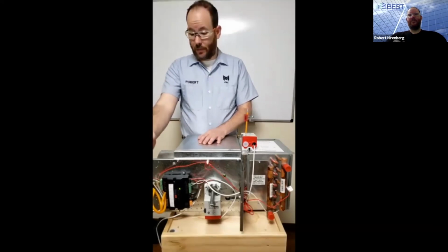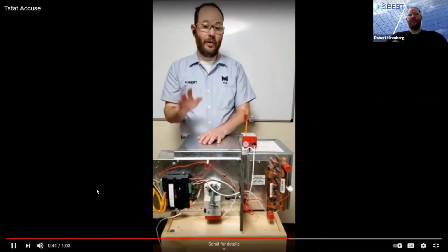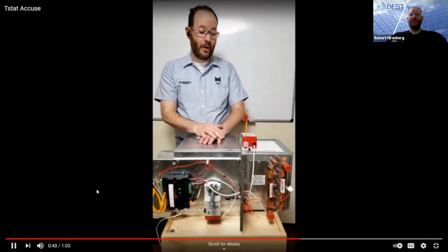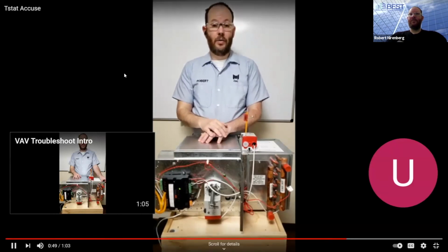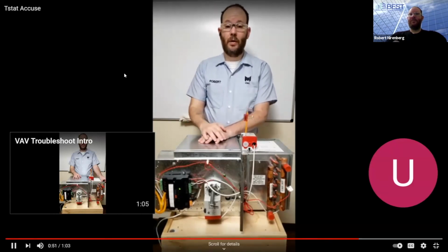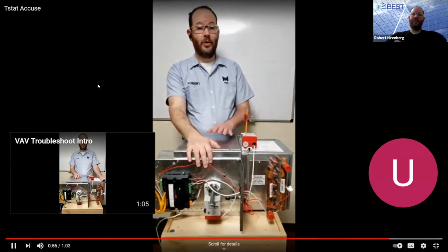And because of the resistance range on the potentiometer, that was always at a high temperature, below 10,000 ohms of resistance. So the system always believed that it was warm and that it needed cooling. So that was why the office was always cold.